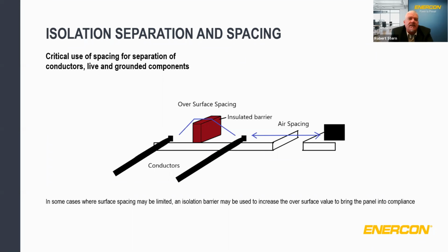Okay, so isolation, separation, and spacing is very vital. Spacing between isolated circuits at different potentials is judged based on the higher potential. Spacing between live parts and metal parts intended to be grounded are always evaluated as grounded parts. Spacing on or within a component is based on the requirements in the standard concerning that particular component. Critical to the design process are circuits and spacings as follows. Between uninsulated live parts and adjacent components, whether it's metal, a conductor, or any other type of component.